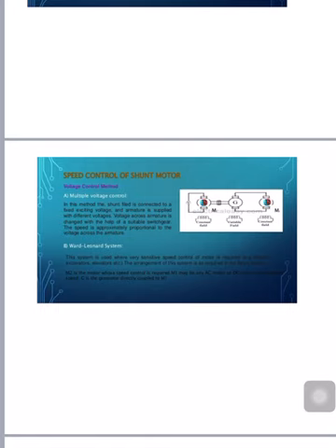We can get very smooth speed control over a wide range, that is from 0 to normal speed of the motor, and the speed can be controlled in both directions of rotation of the motor easily. The motor can run with a uniform acceleration, speed regulation of the DC motor in this Ward-Leonard system is very good, and we have inherent regenerative braking property.